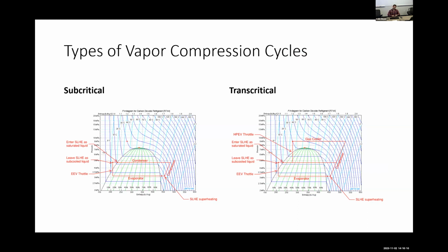So you can use CO2 as a very efficient vapor compression cycle for lower temperature cascade systems, where you're refrigerating the condenser of the CO2 cycle to maintain it being subcritical. When you go transcritical, there's a lot of challenges and additional costs, but there are some things that can really be helpful in a heat pump. So subcritical cycle on the PH diagram, basically you're evaporating refrigerant, you're compressing it, you're condensing it, you're expanding it.